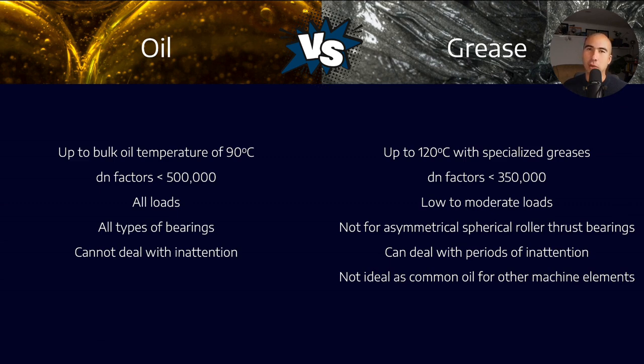With oils, we go up to bulk oil temperature of 90 degrees Celsius, higher with synthetics. DN factors are about 500,000. We can accommodate a wide load range with high viscosity oils, suitable for all bearing types. Oil doesn't deal well with inattention - oils take on environmental contaminants like dust and water because oils are hygroscopic, leading to corrosion. The advantage is that if bearings are part of a wider circulating system, you would use oil.